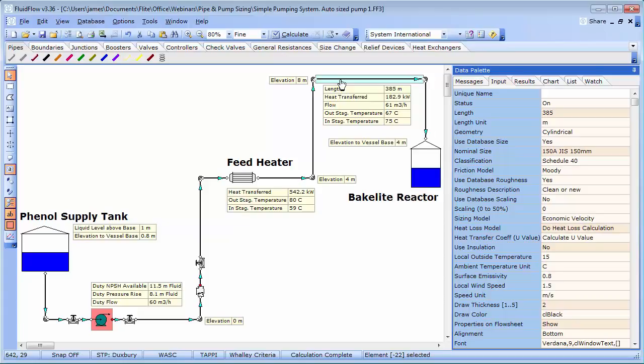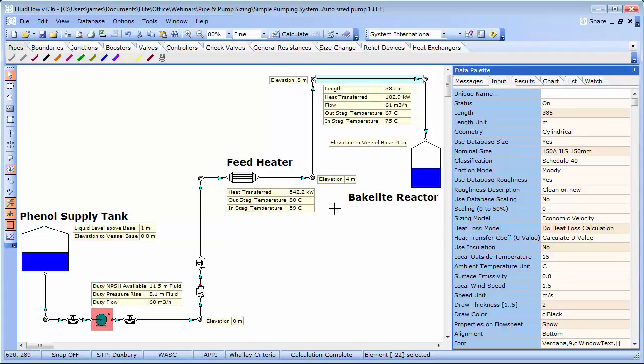Earlier we made reference to pipe heat loss. We are adding some 20 degrees C to the phenol at the feed heater, which equates to around 542 kilowatts of heat energy. Downstream of this heater, we have a considerable length of pipe work, where we are subsequently losing over 182 kilowatts of heat.